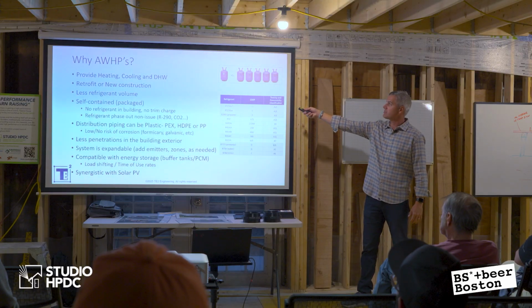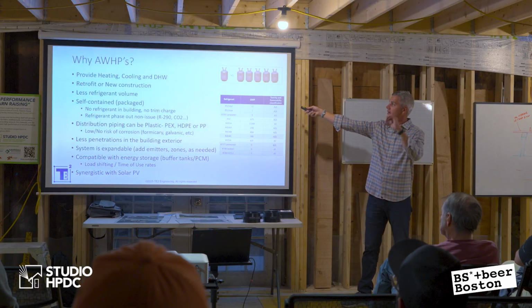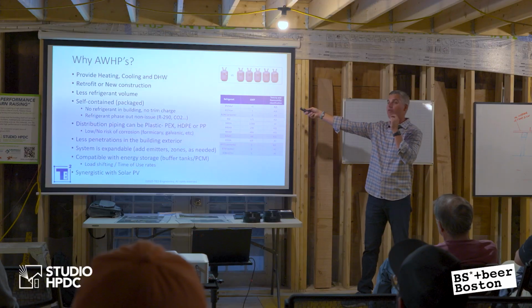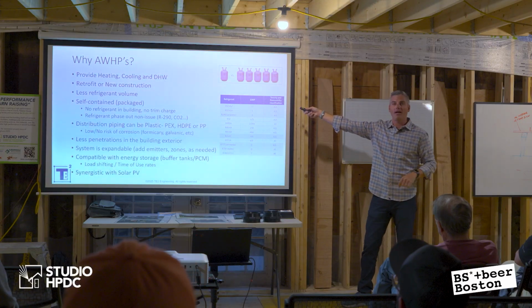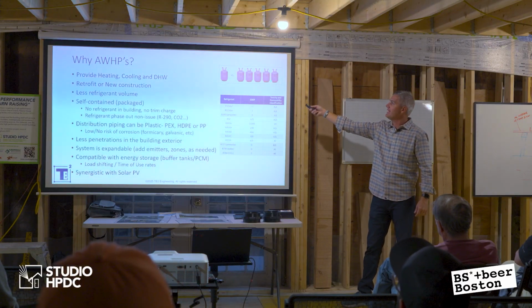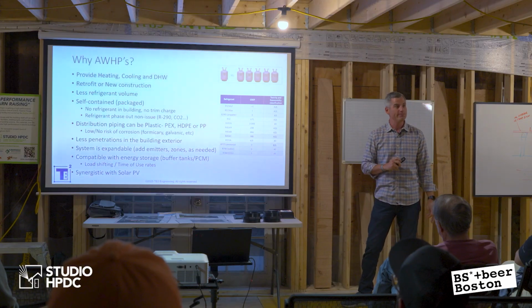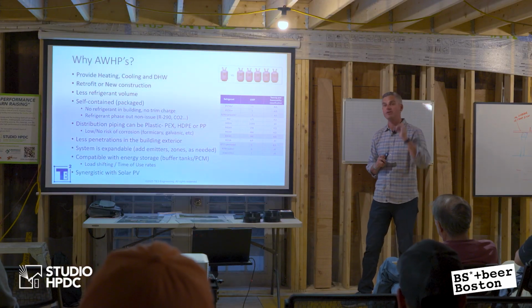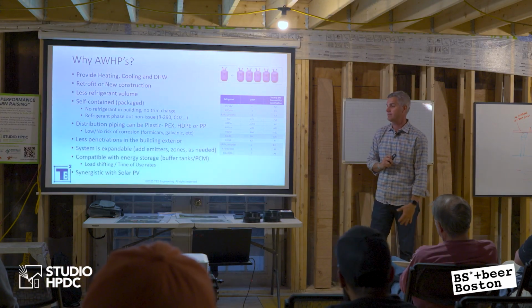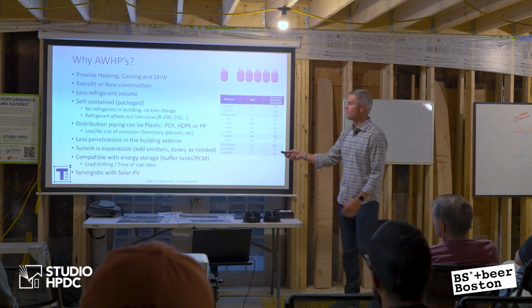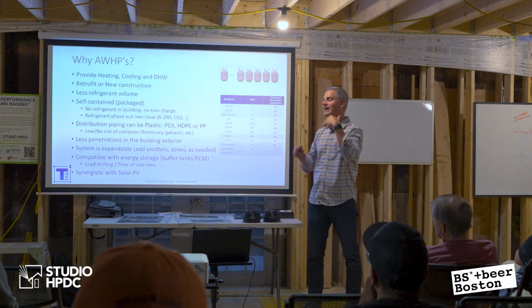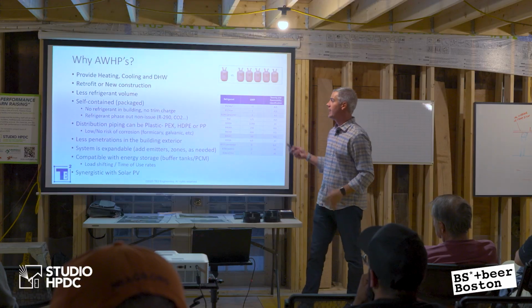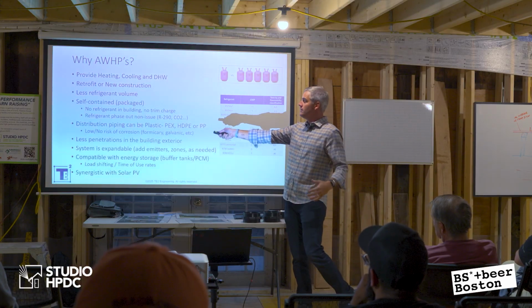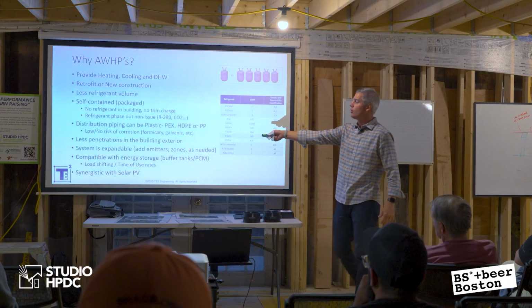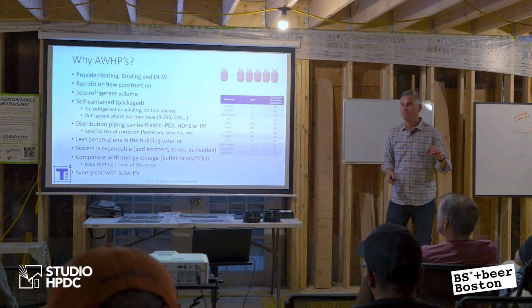Okay, so this is what's installed. This is a single tank that comes hermetically sealed like a refrigerator in an air-to-water packaged monoblock system. This is how much refrigerant I need in the equivalent of a VRF version of that. So if I have a refrigerant leak, which one would you rather have leaking? Right? Less refrigerant volume that has a bunch of embodied carbon aspects to it, operational carbon, etc. Has a big issue with the ozone and global warming potential. Self-contained package, no refrigerant in the building, no trim charge.